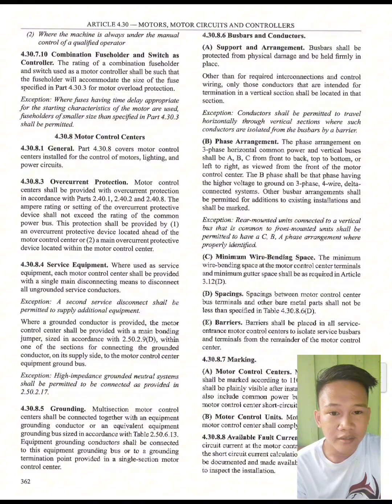Next is phase arrangement. The phase arrangement on a three-phase horizontal common power and vertical buses shall be A, B, C, from front to back, top to bottom, or left to right as viewed from the front of the motor control center. The B phase shall be that phase having the higher voltage to ground on 3-phase, 4-wire delta connected systems. Other busbar arrangements shall be permitted for additions to existing installations and shall be marked. So, exemption: rear-mounted units connected to a vertical bus that is common to front-mounted units shall be permitted to have a CBA phase arrangement where properly identified.